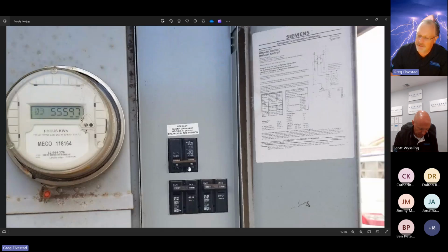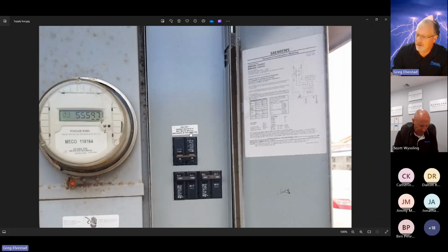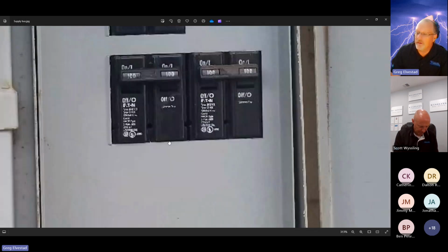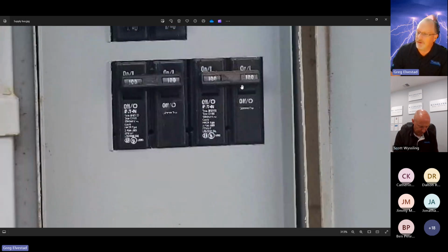You can't have a breaker in this position here if you're using a QN style breaker because it occupies the entire width of that space. So that's a code violation. But I wanted to use the panel to show that you are able to have a breaker here feeding load and another breaker here feeding load, or if this is empty, you can park solar there. So make sure to make note of questions you might have as we go along here so that we can bring those up and talk about them as we proceed.